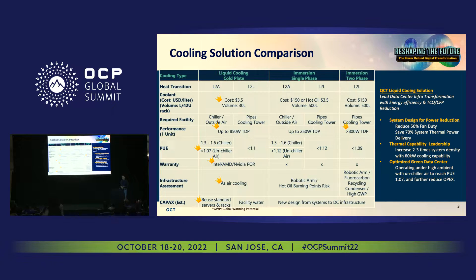They all require different infrastructure facilities, but in terms of performance based on actual results, liquid cooling can perform quite well, even compared with emerging two-phase solutions. We are looking at 850W TDP. When comparing our liquid cooling solutions using non-chiller air, we are looking at as good as 1.07 or lower PUE. About warranty — that's a big issue. Today, no IC vendor is able to provide warranty for emerging cooling.